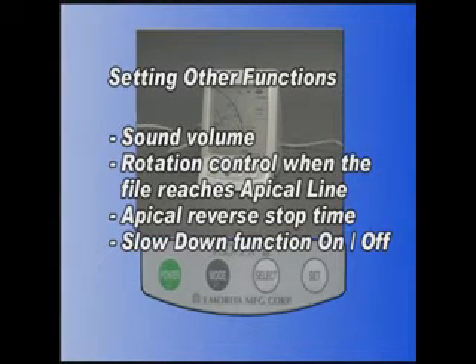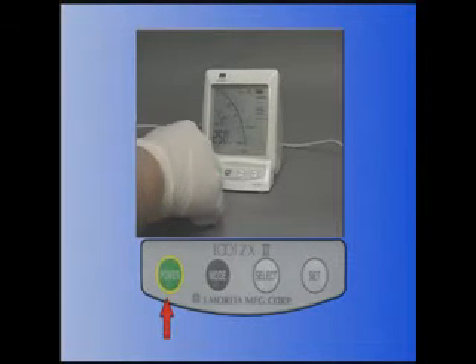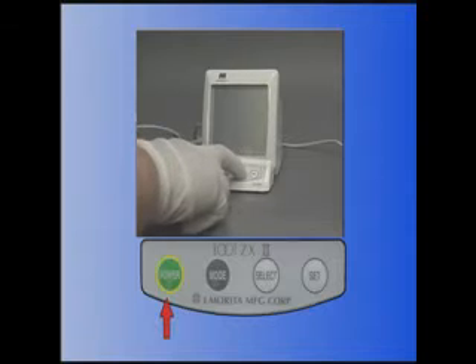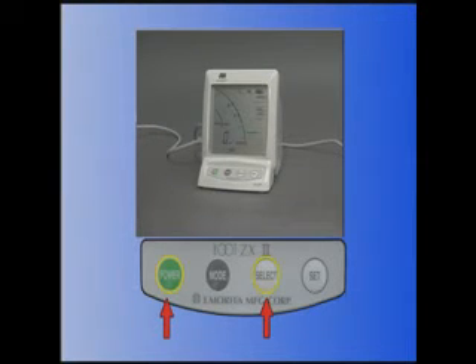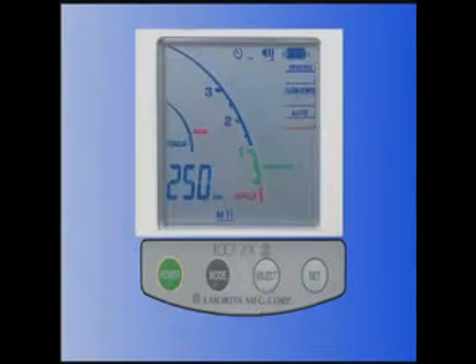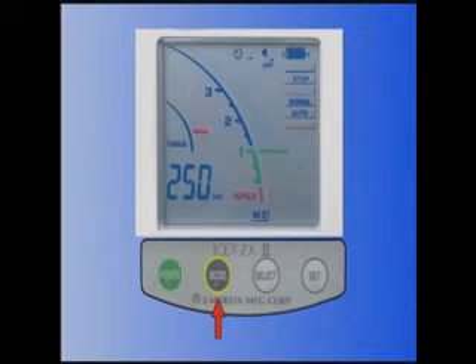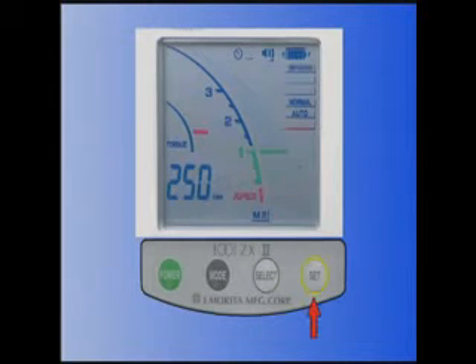Other setups, such as alarm sound volume, can be changed by doing the following. Turn off the unit. Press the select switch and turn the power back on without releasing the select switch. Release the select switch and press the mode switch to select M1, M2, or M3. Press the select switch to select the item you want to change. Once the item starts flashing, press the set switch to change the setup. The setup is saved when the item stops flashing. Once again, all memory settings will be retained even after the unit is turned off.